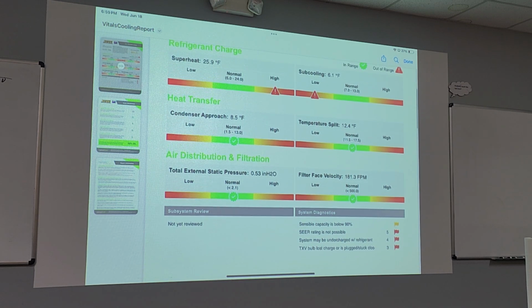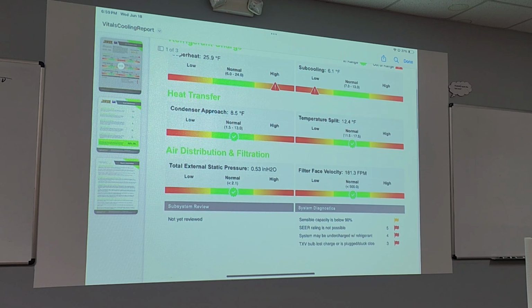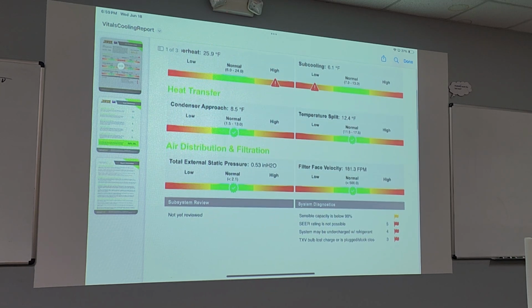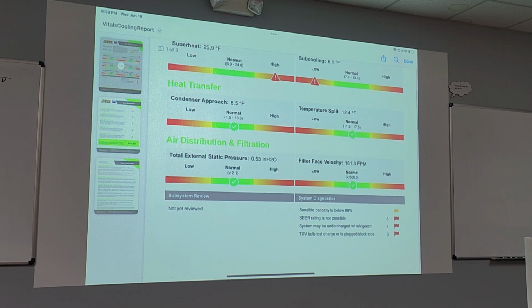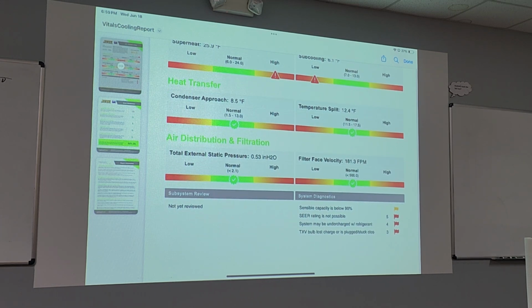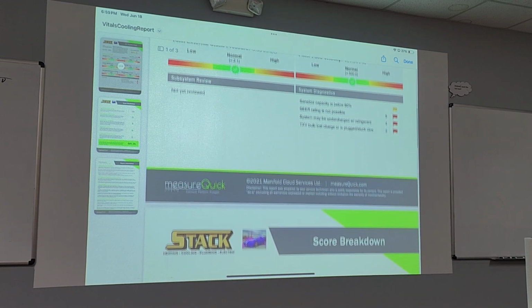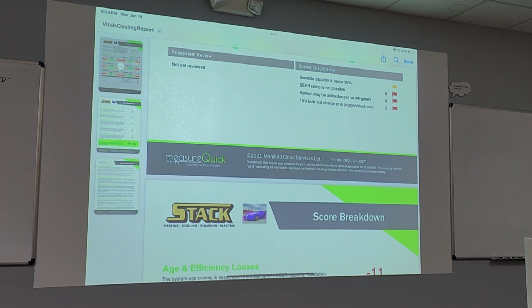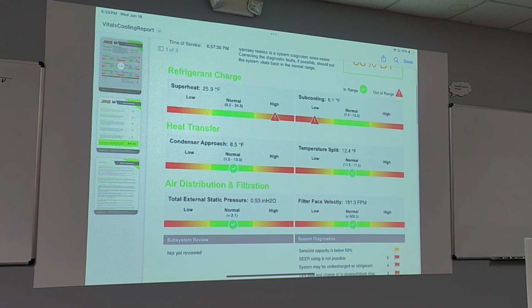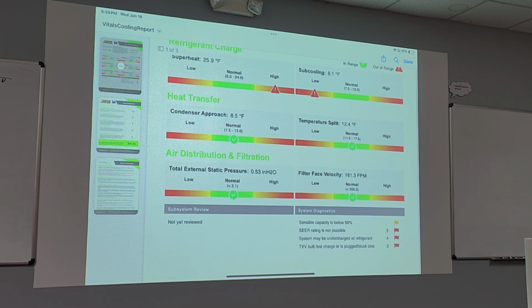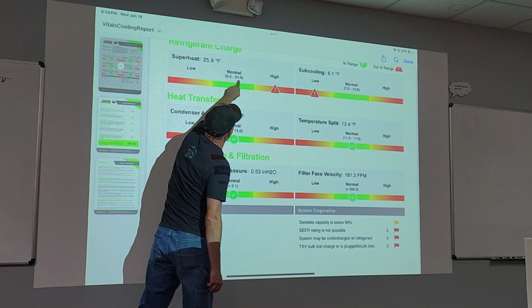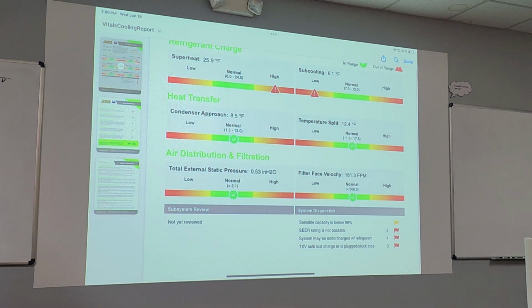So right now my superheat and subcooling is a little bit out of whack. Not by much, but a little. You wanna explain why the superheat and subcooling are out of whack? Well, could be a few reasons, and we kind of have diagnostics on this. If you look there, right column, subcooling is low. Subcooling target's 10 degrees, and superheat, what's our tolerance? Up to 24 degrees superheat. If you look right there, it puts the tolerance in here. You're allowed 24.